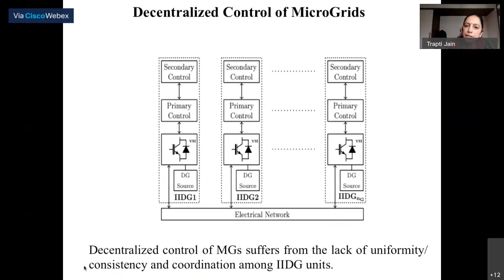Then we have the control architectures: decentralized, centralized, distributed, and hierarchical control. In the decentralized control, each individual DG unit, IIDG, meaning inverter interfaced DG units because they are interfaced through inverters, has its primary control, and each primary control is connected with a secondary control. This is local and utilizes local measurements. The main drawback of this scheme is that proper coordination is not possible among the various IIDG units, because you are not aware of the control strategies or conditions of the other units.